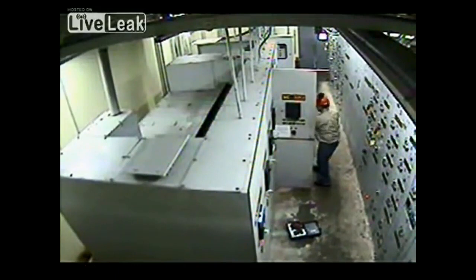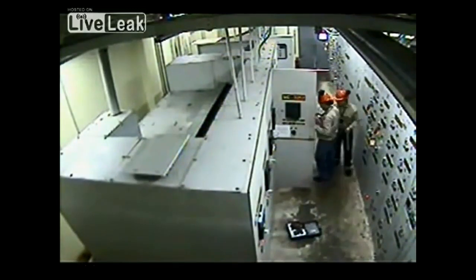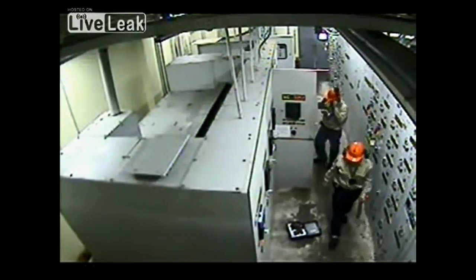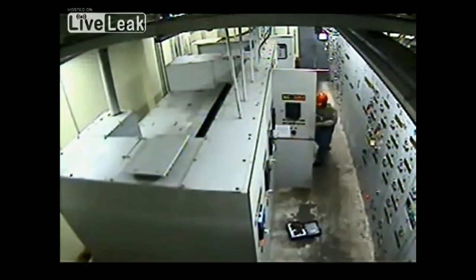You see him turning the thing? The other guy, is he in there too? He is, but he leaves before it happens. What's happened is something's wrong with the back of the breaker where the blades that go in are not quite right. That creates a short, and there's so much energy inside this cabinet that it creates an arc flash. Then the arc flash creates an arc blast. So he's safe now - if it had stayed in there...